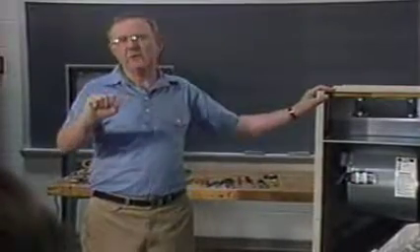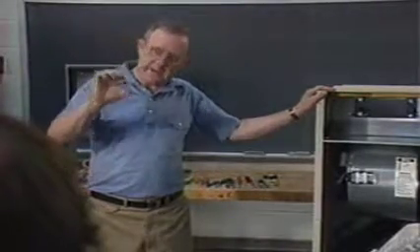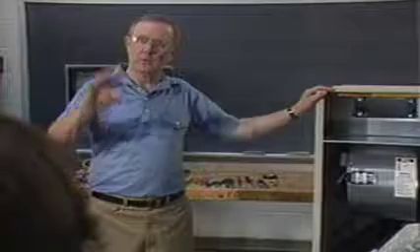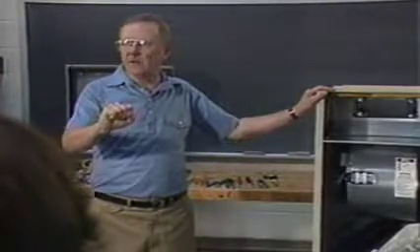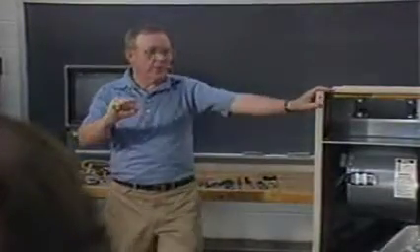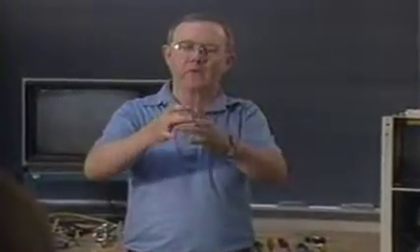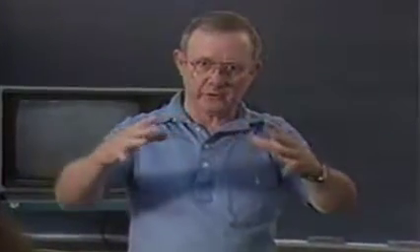Now, if the suction line is so cold that when you hold on to it, that's a real good sign that there's liquid in the suction line instead of vapor — because liquid will draw the heat out of your hand much faster than vapor, and it'll become painful to hold on to. If there's vapor in the suction line, when you grip it, your hand will warm up the vapor to the point that it won't be uncomfortable to hold on to. The compressor in this unit was also sweating all over. A typical compressor should sweat right around the suction line where it enters the casing, maybe a couple of inches — this compressor was cold and sweating all down the sides, indicating liquid refrigerant flowing back into the compressor.